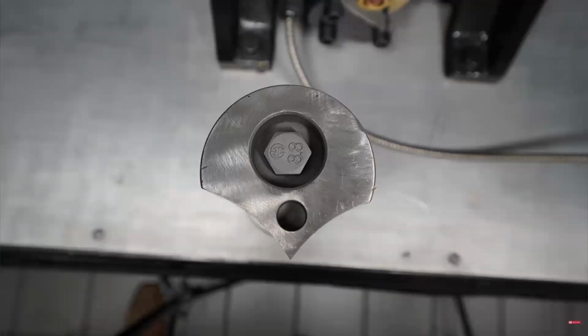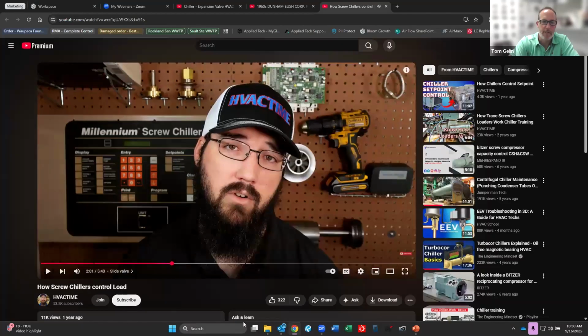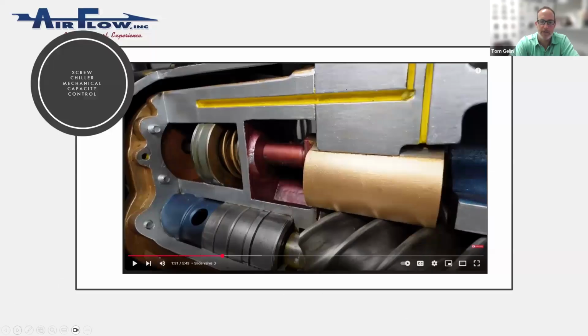It's based on what our RLA is—we run based off a percentage of that. That's a neat little feature about screw chillers: you can control capacity in part mechanically, and then also with the variable frequency drive on it. That's why it's called positive displacement when it moves.